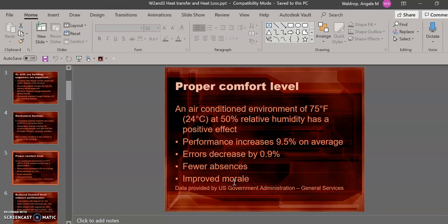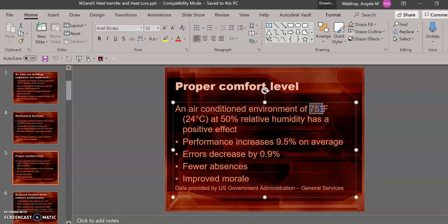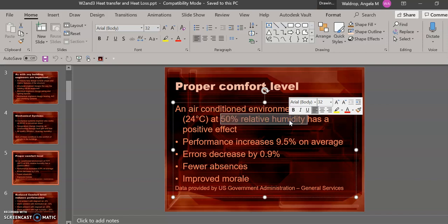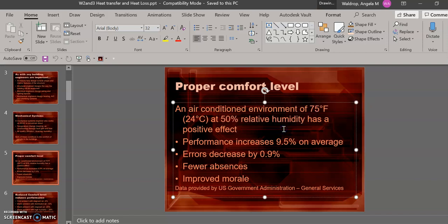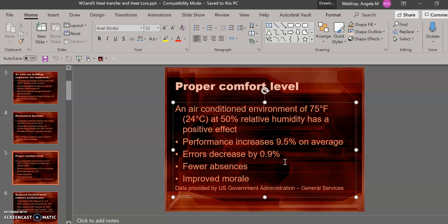This slide shows you the ideal conditions that mechanical engineers shoot for when they are designing the air conditioning and heating systems for a building. The ideal conditions are 75 degrees Fahrenheit and 50% relative humidity. People seem to be the most comfortable and productive at these conditions. However, these conditions are not always met. And this is important to know for your assignment. In the winter, when it's extremely cold, they try to aim for 68 degrees and have a lower humidity. The air is a bit more dry. In the summer, when it's extremely hot, they try to aim for 78 degrees and have a higher humidity. Adjusting the ideal conditions in these extreme temperatures allows the system to be a bit more efficient.